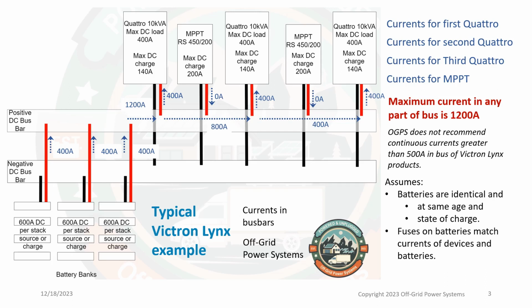Lynx products. However, at Off-Grid, we don't recommend more than 500 amps continuous on the Lynx products. The Lynx bus bar should only be able to carry 720 amps continuously, with a 30 degree temperature rise in free air. It is not in free air, and there are few vents, and that's why we recommend 500 amps. It can carry 1000 amps for short periods of time, but not continuously. Overheating can lead to serious issues in this or any other part of your system.